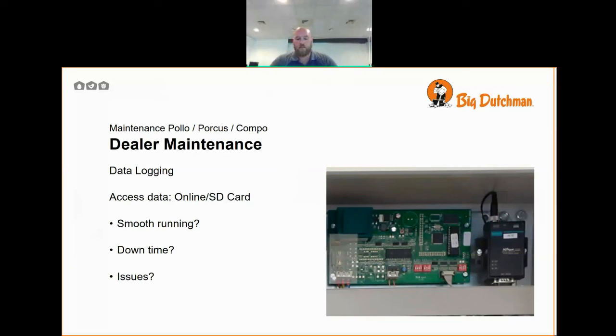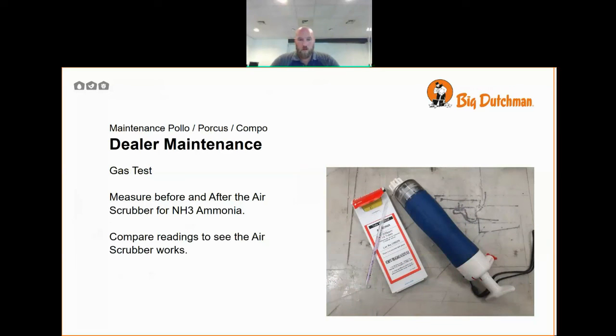On the Moxa modem, obviously you can access this from a distance, and in the same way you can check through if there were any issues, or if there's any history of alarms repeating. And finally, gas testing. We measure before and after the air scrubber for NH3 ammonia, and comparing these two readings, we can get a percentage of how well the air scrubber is performing. Is it a 70% air scrubber? Is it a 90% air scrubber? We need to make sure that we are actually reducing correctly, and if not, why not?